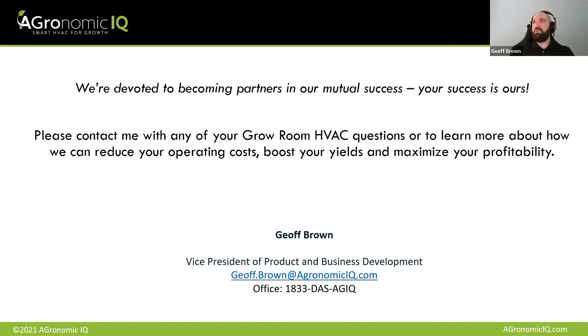Yeah, so this is getting into the weeds of control algorithms, but basically the user sets a target temperature and relative humidity for the space. So, just for grins, middle of a flower cycle, 76 degrees Fahrenheit and 55% relative humidity would be not atypical. And so in setting that, the equipment will then look at the airstream coming back to the equipment.